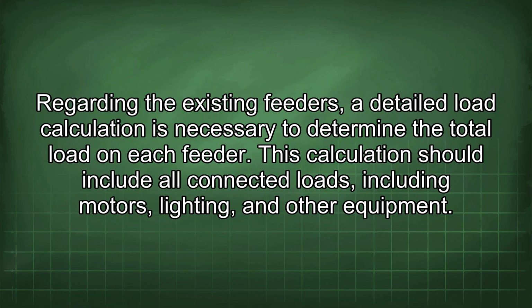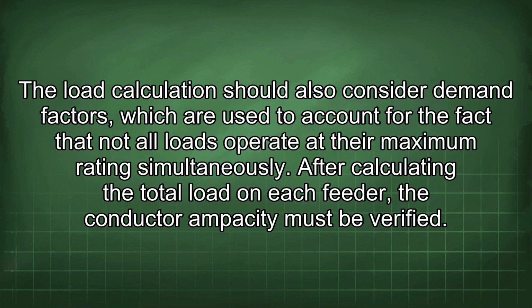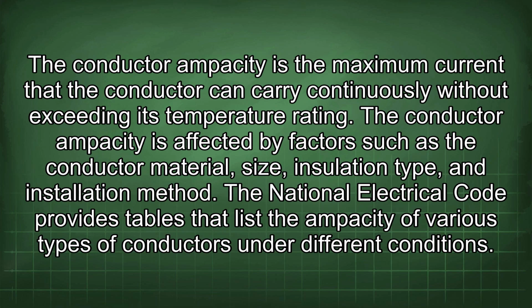Regarding the existing feeders, a detailed load calculation is necessary to determine the total load on each feeder. This calculation should include all connected loads, including motors, lighting, and other equipment. The load calculation should also consider demand factors, which are used to account for the fact that not all loads operate at the maximum rating simultaneously. After calculating the total load on each feeder, the conductor ampacity must be verified. The conductor ampacity is the maximum current that the conductor can carry continuously without exceeding its temperature rating. The conductor ampacity is affected by factors such as the conductor material, size, insulation type, and installation method.